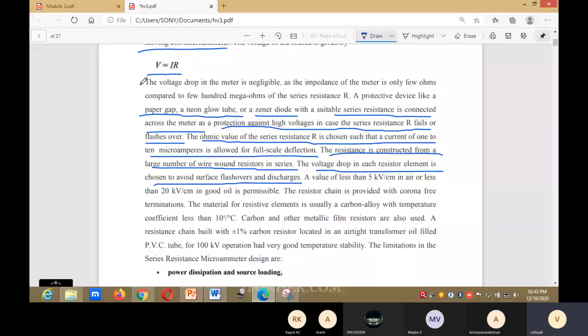One thing you need to remember: the voltage drop in the meter is negligible as the impedance of the meter is only a few ohms compared to a few hundred megaohms of the series resistance. And the voltage drop in each resistor element is chosen to avoid surface flashover and discharges. A value of less than 5 kV per centimeter in air or less than 20 kV per centimeter in good oil is permissible.